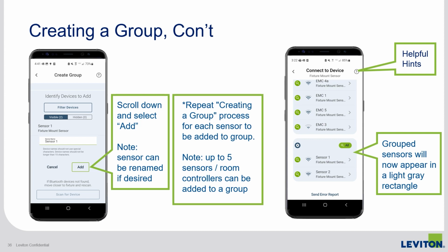To add additional sensors or room controllers, you will repeat the same process. The Identify button can be used to confirm you are adding the correct device. Up to 5 sensors or room controllers can be grouped. Again, it's okay to have mixed groups of sensors or room controllers. Once a group has been formed, the devices will appear with a light gray background on the scan page to show which devices are grouped together.